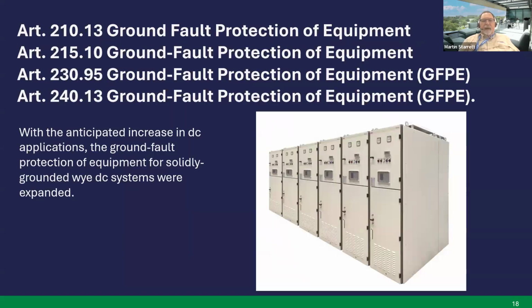Next slide. I'm going to look at four things at once here, for ground fault protection of equipment, GFPE, not only in the branch circuit article, but the feeder article, the service article, and the overcurrent protection article. With the anticipated increase in DC applications, the ground fault protection of equipment for solidly grounded wye DC systems was expanded. So in each one of these articles, they've added the DC, because a lot more of that is being used now.